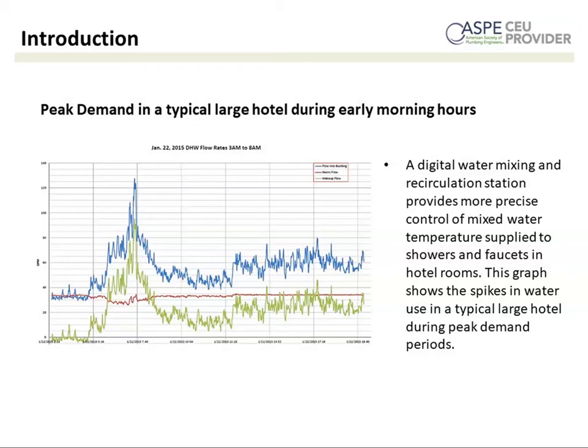And at peak hours, which were kind of early morning hours when you'd expect everybody up and showering, 500-room hotel, and it was about at 85% occupancy. The maximum flow into the building was just over 120 gallons per minute, much, much lower than was anticipated. So when this facility looks to do an addition or a renovation, this type of data will be very, very useful to them when they go to sizing their next valve.